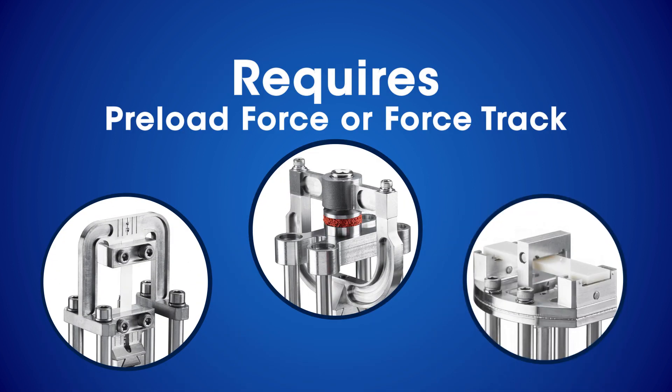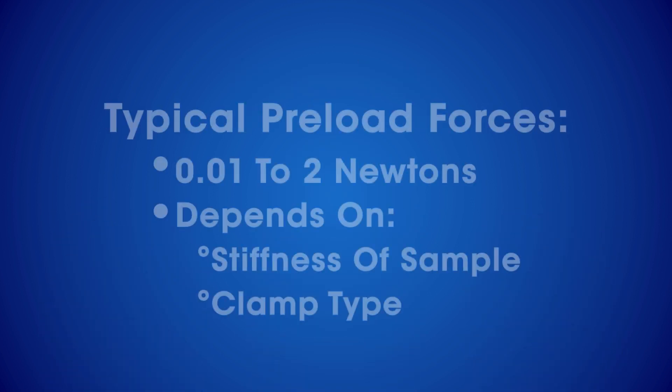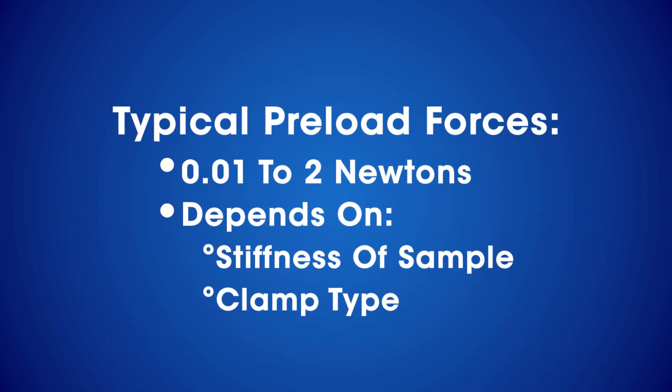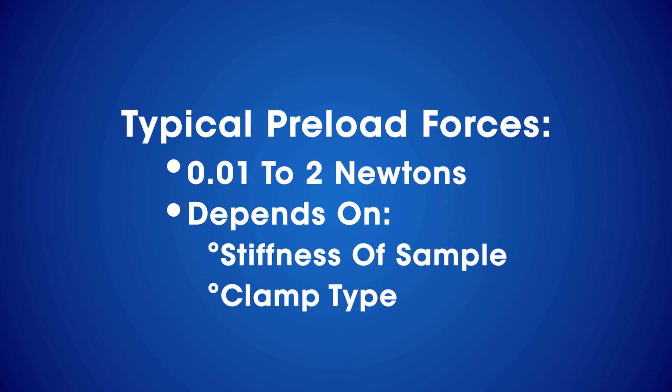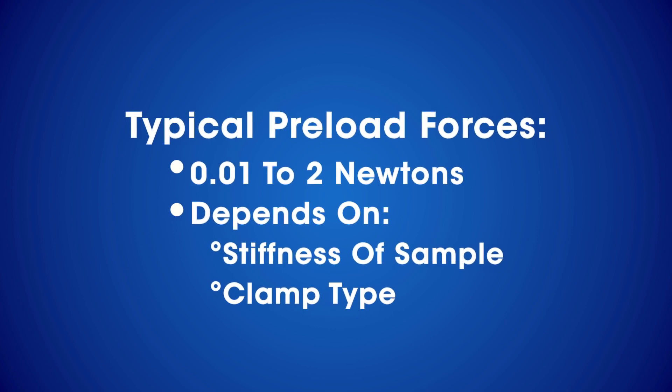The tension, compression, and three-point bend clamps do. Typical preload forces are in the range of 0.01 to 2 Newtons depending on the stiffness of the sample and clamp type.